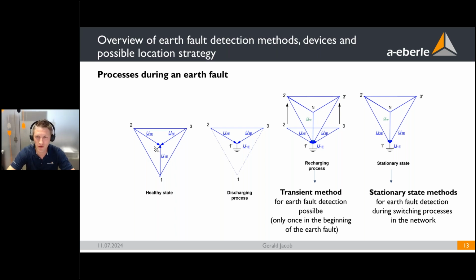If there's an earth fault on one phase, then in the beginning you have the healthy state, then the earth fault begins. You have a discharging process of the affected line, of the affected phase, and in the end you have a recharging process. This is in the first 5 milliseconds after the earth fault started, and then you get into a stationary state if it was not only a transient behavior, but an ongoing earth fault on one line. For this recharging process and the stationary state, we have different earth fault algorithms. For the transient method, this is a very reliable one. There we have 2 different methods.